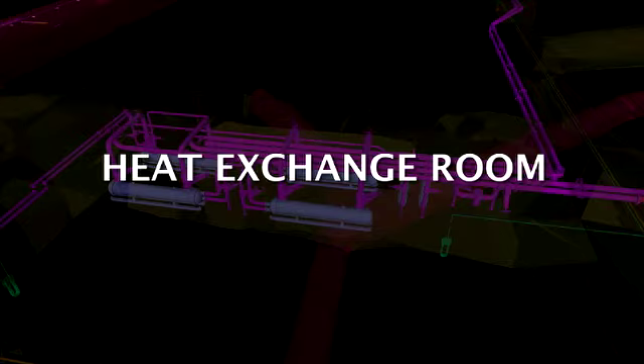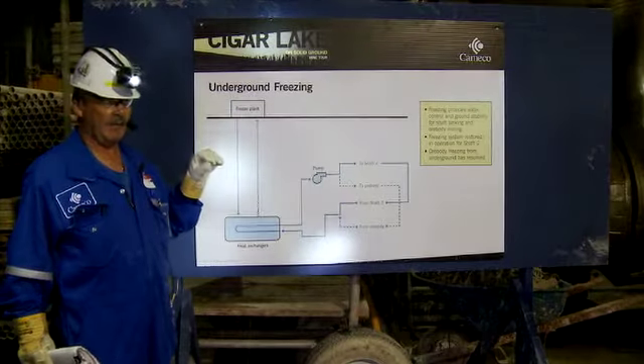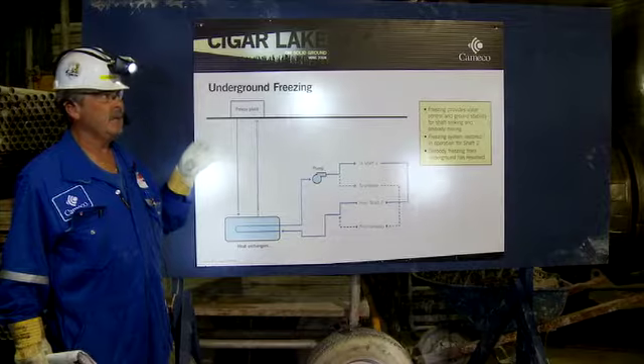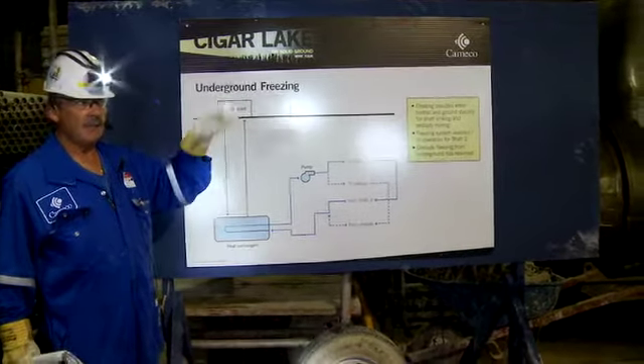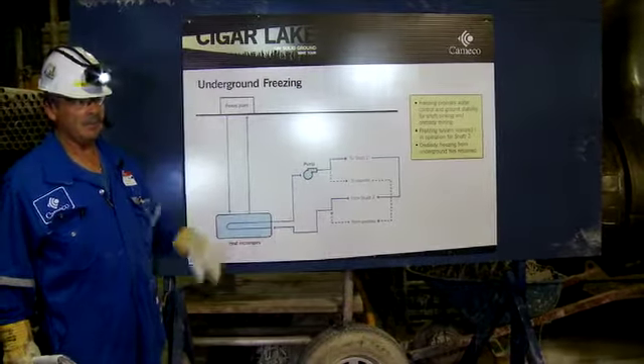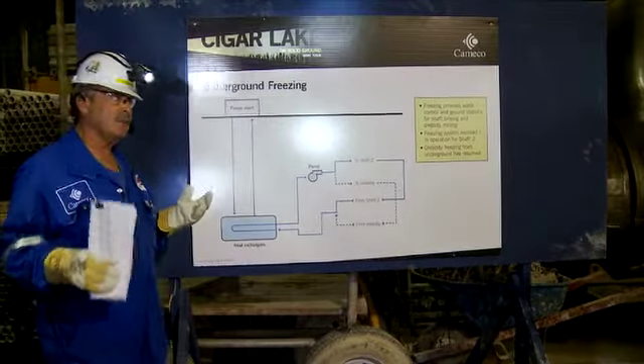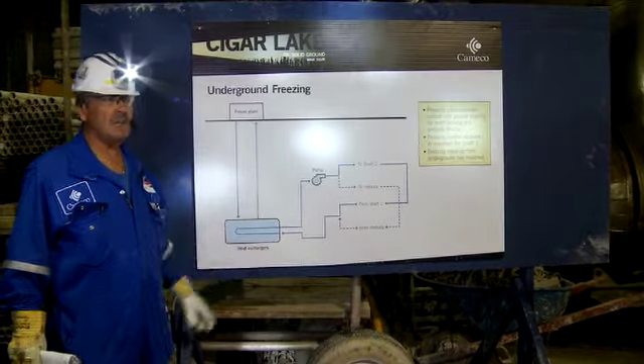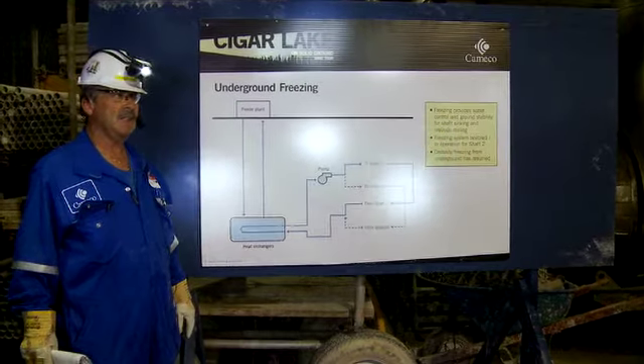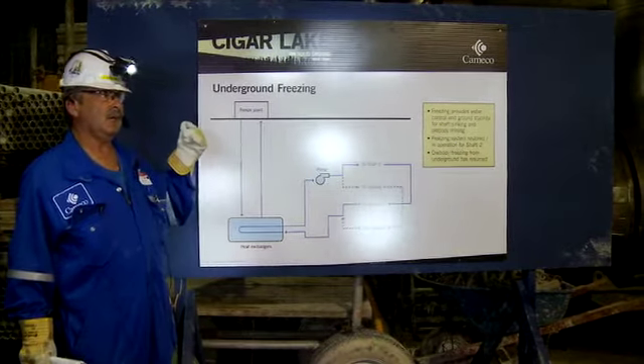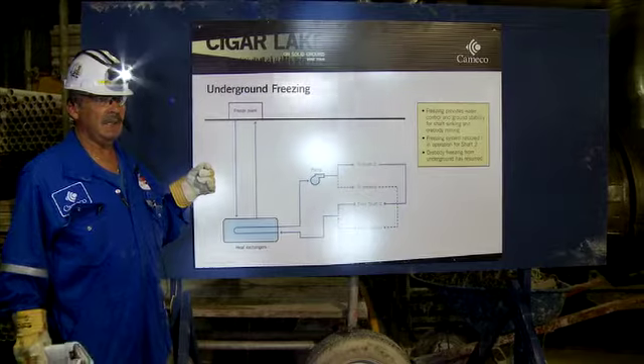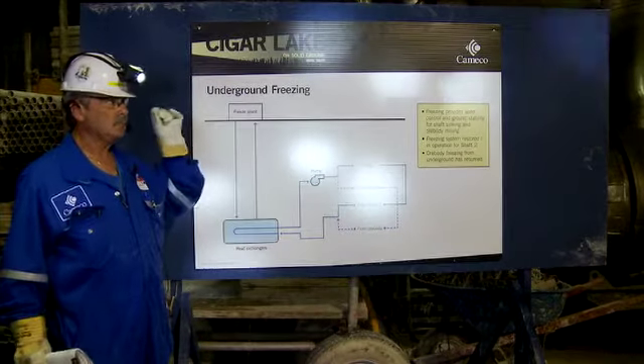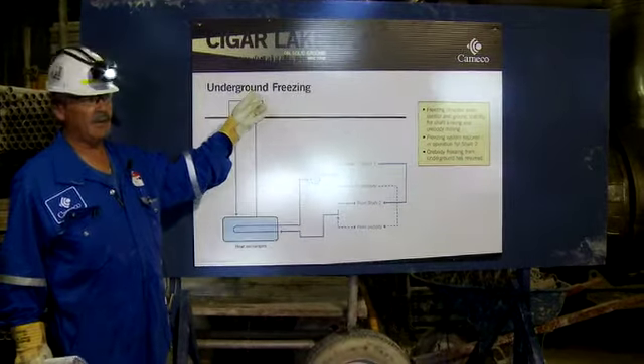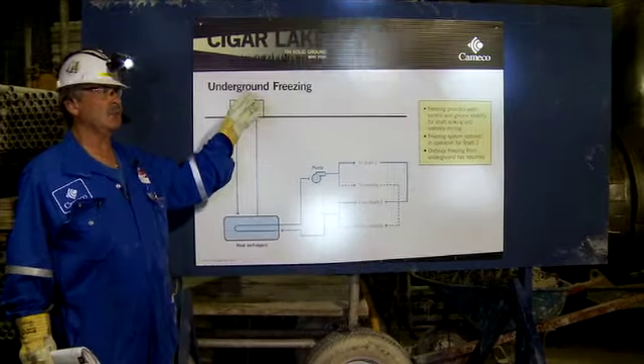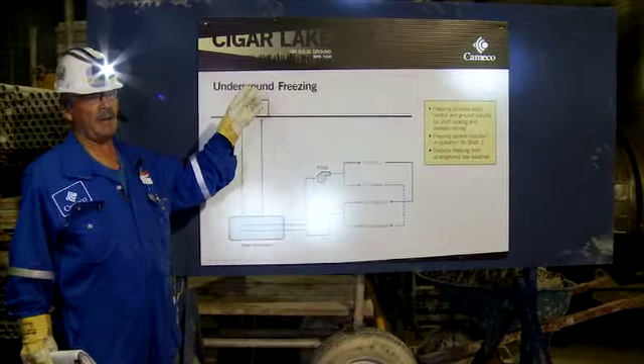We have the heat exchangers here, so we have a low pressure system on the level, approximately 100 psi, and then we have the high pressure system that goes into the shaft and up to the freeze plant. The efficiencies are very good. It comes down at about minus 38 degrees, and it only loses 1 or 2 degrees in the heat transfer. And the brine going out to the areas goes out about minus 37, coming back around minus 34, minus 35 degrees Celsius.